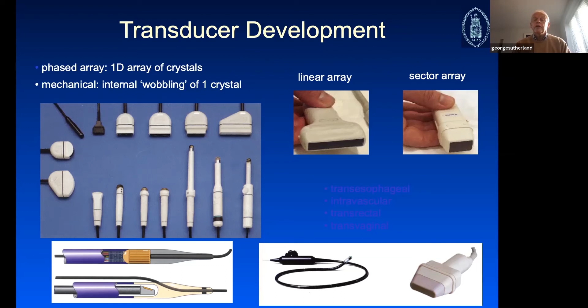Although Frazen described ultrasound obtained from the esophagus in 1957, it was only in the early 90s that a combination of Japanese and ourselves in Thorax Center developed this further. Peter Hanrath had been instrumental in giving the idea, and we went to Old Delft in Rotterdam, and they produced, via an Olympus gastroscope, a probe where they took out some of the fibers and replaced them by ultrasound cables and crystals, so that at 2.5 megahertz we could actually see a 2D image from the esophagus. This has been so far refined over the last years that we now scan in relatively high resolution in 3D echo from the esophagus. So probe development, intravascular probes, everything, fantastic developments in probes.